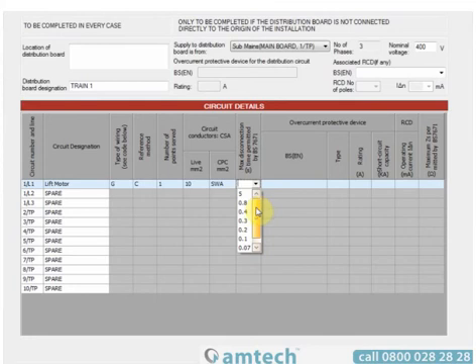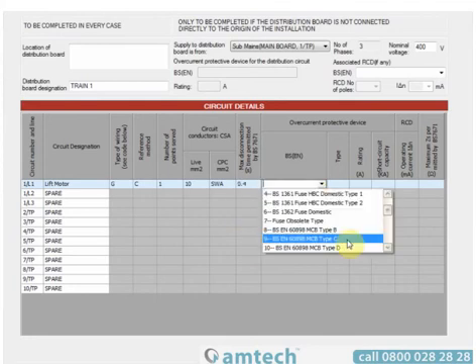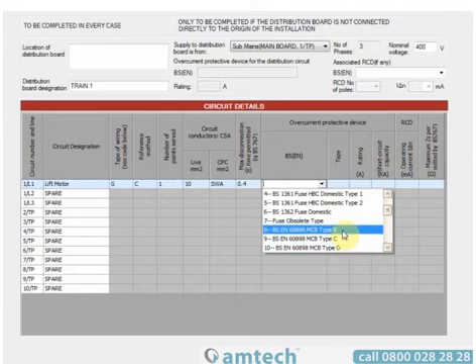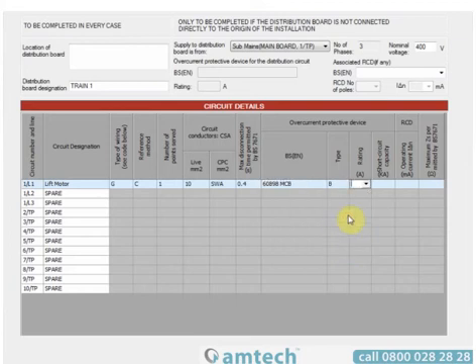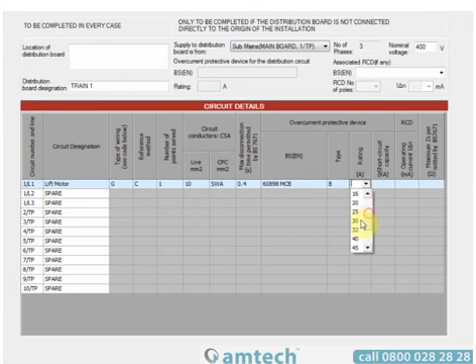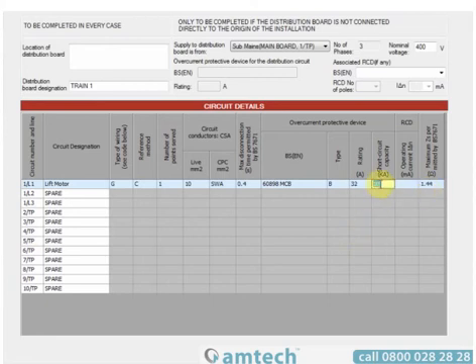I'm going to select 0.4 here. My device is going to be a BS 60898 MCB type B and I'm going to select the rating of 32 amps. As you can see, it's pre-entered the value of maximum ZS and also the value for short circuit capacity.